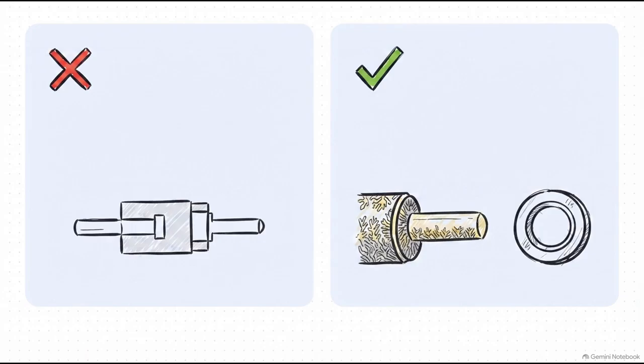Instead of just one single contact point, they brought in hyperboloid pins with 10 to 20 parallel contact points. So if one micro moves, 19 others are still carrying the signal. And the real game changer? To stop those EDM bearing sparks, they added dedicated shaft grounding rings. These rings safely brush against the shaft, taking that 370-volt charge and draining it right into the casing before it ever touches the bearing oil.